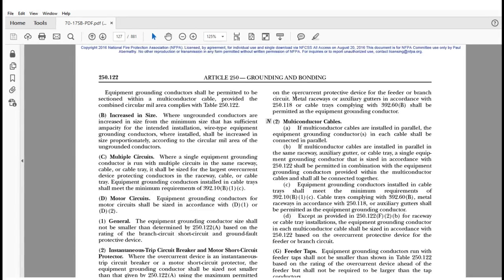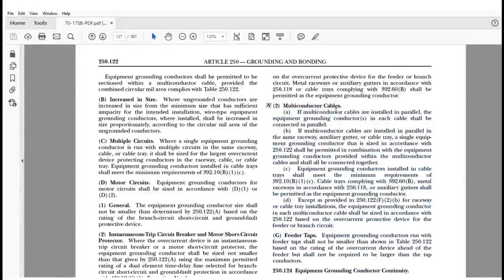Now it goes on to say, look, I am reminding you again that if it is a metal raceway or a metal auxiliary gutter in accordance with 250.118, then it qualifies as an equipment grounding conductor and you don't need to do what we just talked about. Or if it's a cable tray that is listed and identified for use in 392.60(B) as an equipment grounding conductor and it meets all those provisions as we see here, then it can also be considered an equipment grounding conductor, and you'll be in compliance. That's pretty simple, broken down pretty easy to understand. You only have to identify whether it's a single raceway or multiple raceways when you're needing to run those parallel applications.